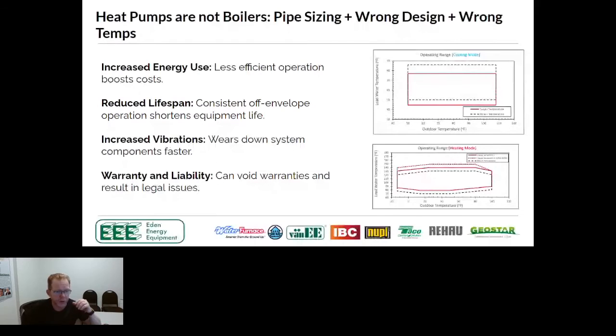So sort of continuing, what's going to happen if we do this? Well, we're going to have increased energy usage. The unit is going to cycle a lot more, which is going to reduce the lifespan. So what's going to happen is your heat pump's going to fire up with half the flow it's supposed to have. It's going to hit its thermal limit. It's going to shut off. It's going to clear that thermal limit. It's going to just keep doing that. It's going to cycle over and over and over again until you either fix it or something potentially could fail. So that's where the reduced lifespan comes from.